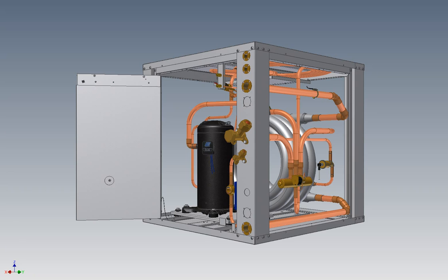The ATW series features the same robust components found in our W series geothermal heat pumps: heavy duty water coils, swing-out electrical box allowing four-side servicing, two-stage Copeland Ultratech compressors, suction accumulator and start capacitors as standard equipment, and de-superheaters with ECM circ pumps. Unlike standard products, our air source machines feature electronic expansion valves for precise superheat control so we can squeeze the most efficiency out of the unit at all times.